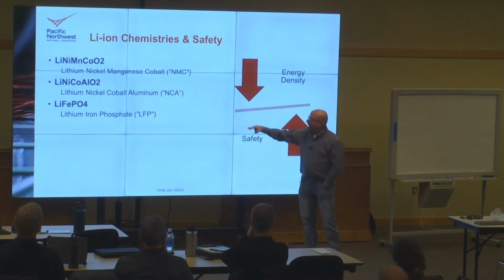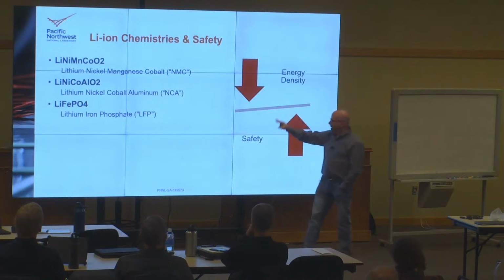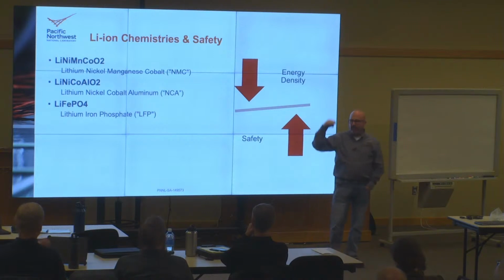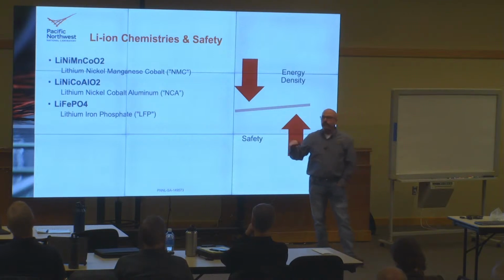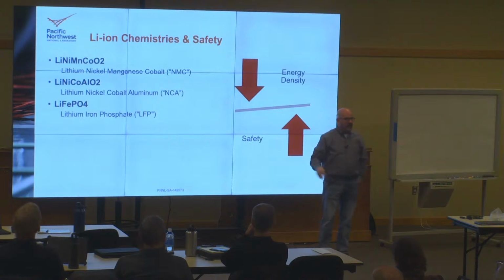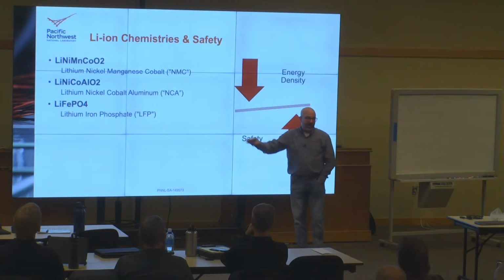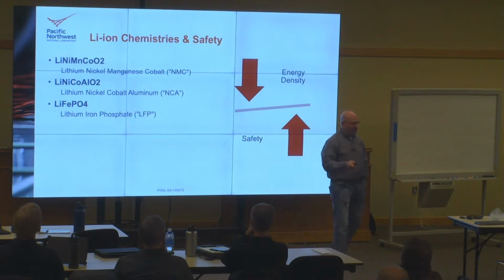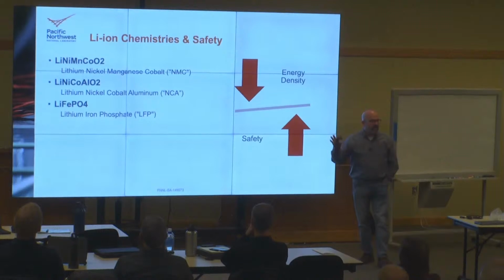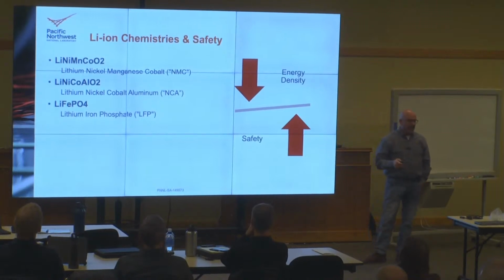As we go down in energy density to LFP, the safety increases. But let me say one thing that's really important: all of these can go into thermal runaway if raised to a high enough temperature. LFP is not immune from thermal runaway, it just takes a higher temperature. There are some other issues with LFP I'll touch on later, but in general it's considered a safer chemistry.